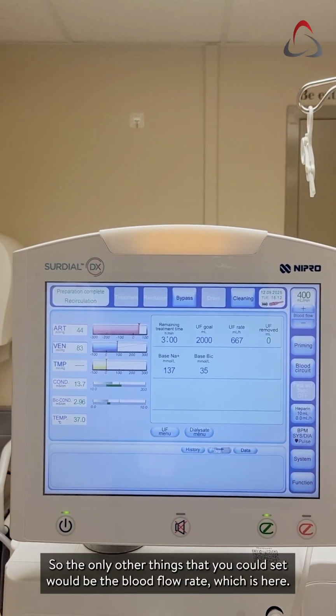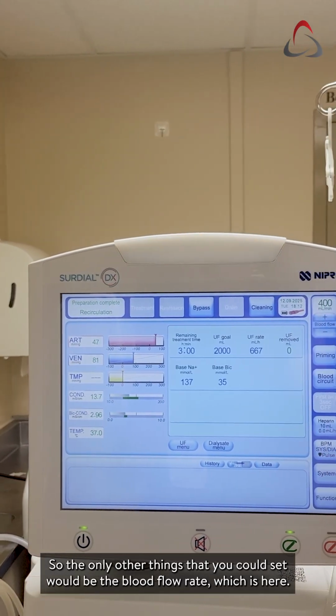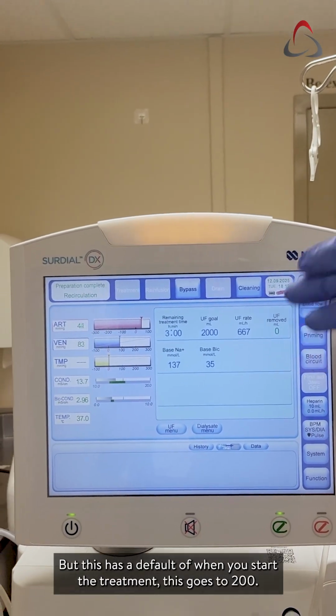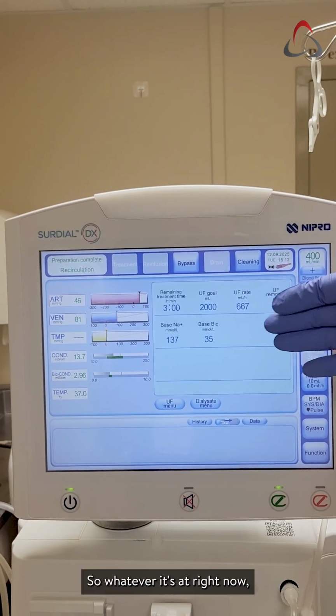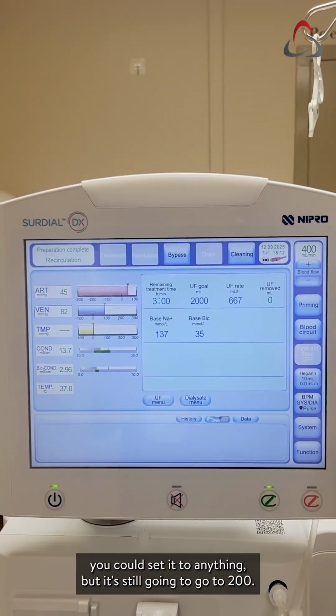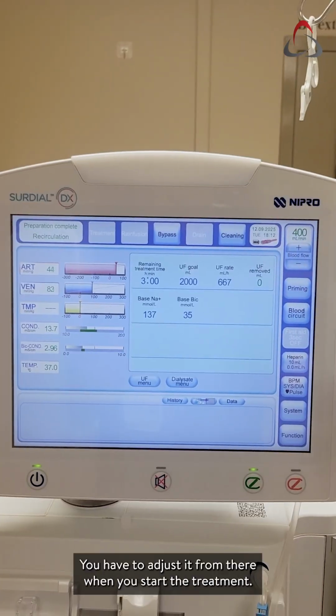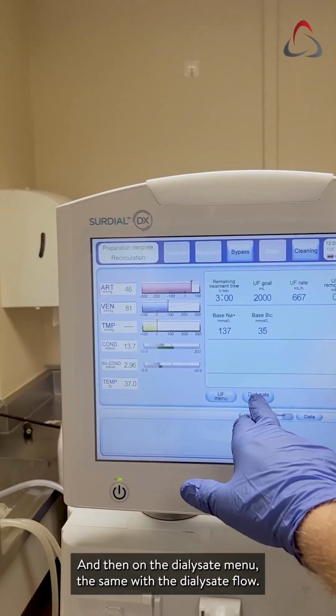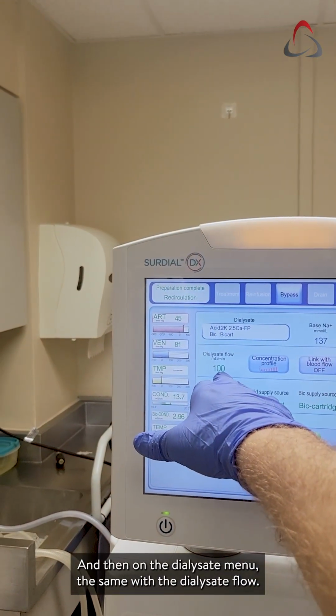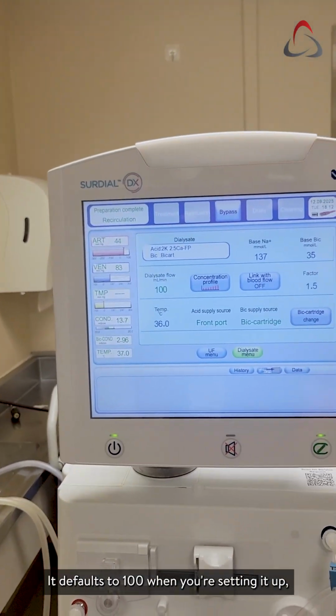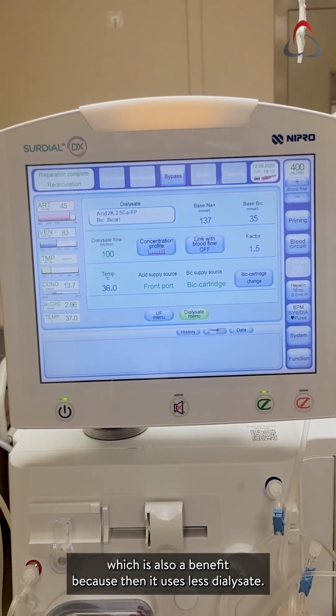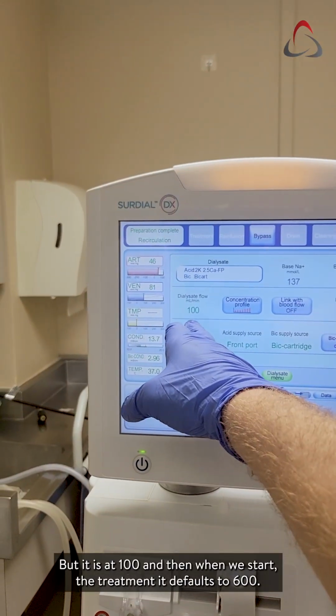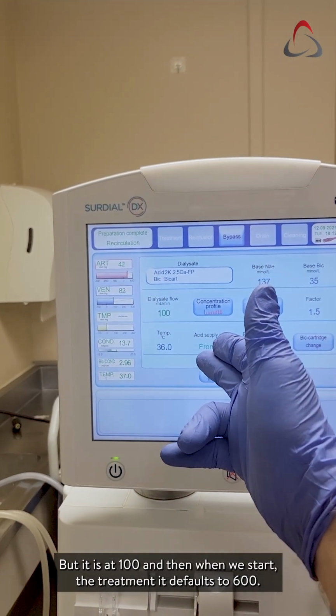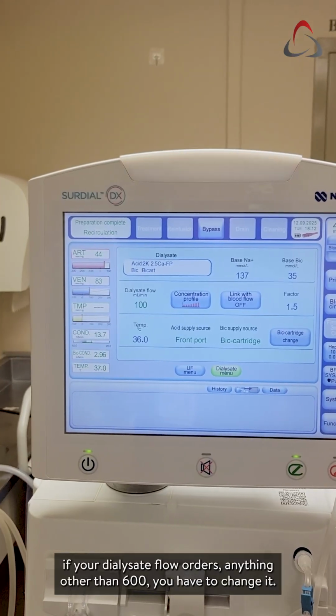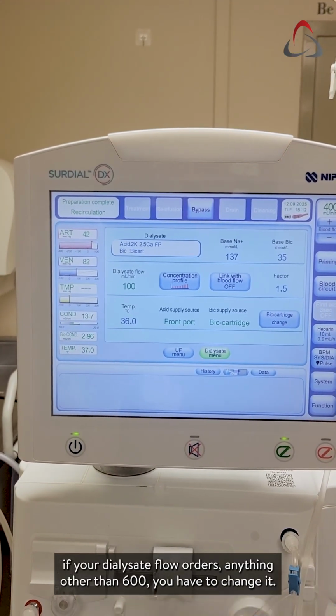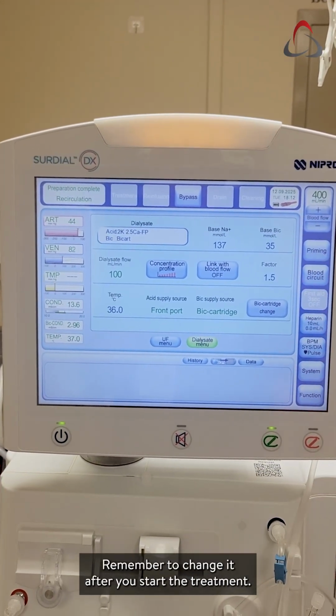So the only other things that you could set would be the blood flow rate, which is here, but this has a default of when you start the treatment, this goes to 200. So whatever it's at right now, you could set it to anything, but it's still going to go to 200. You have to adjust it from there when you start the treatment. And then on the dialysate menu, the same with the dialysate flow, it defaults to 100 when you're setting it up, which is also a benefit because then it uses less dialysate, but it is at 100. And then when we start the treatment, it defaults to 600. So if your dialysate flow order is anything other than 600, you have to change it. Remember to change it after you start the treatment.